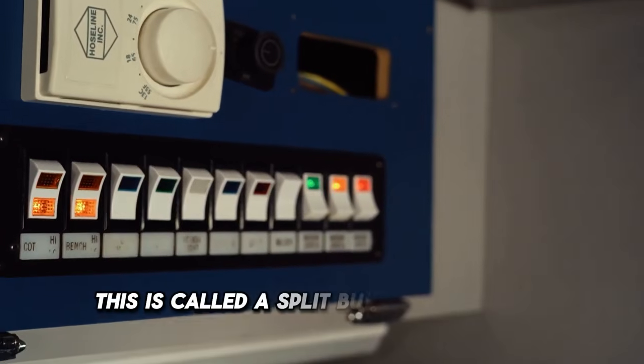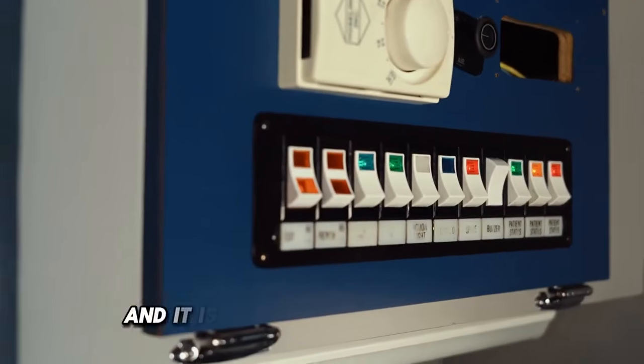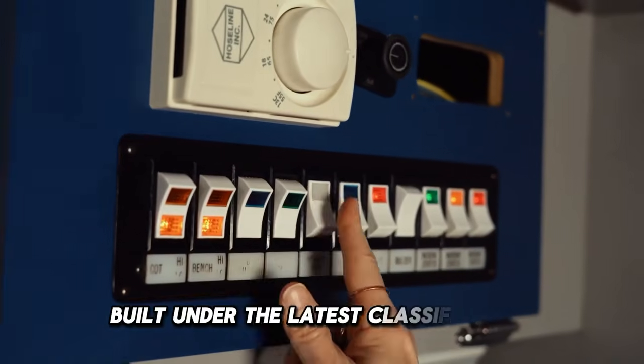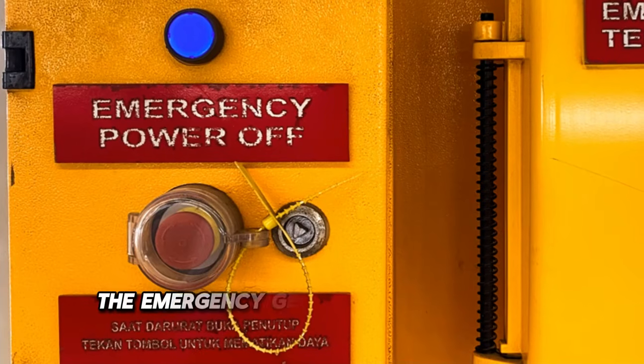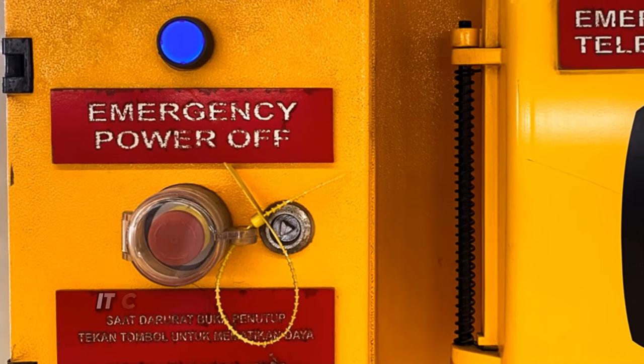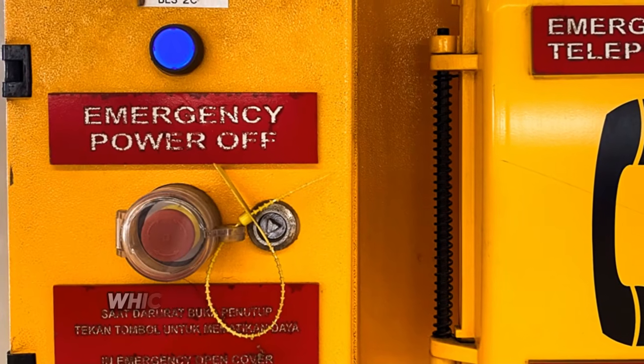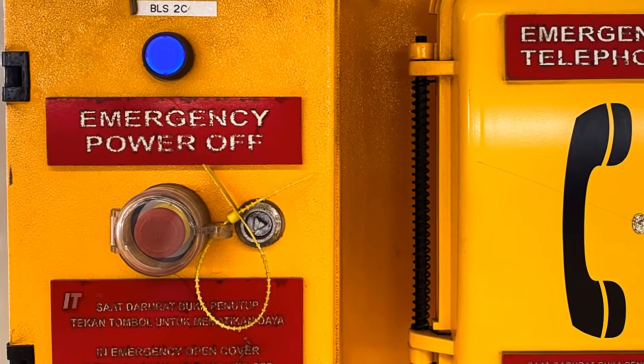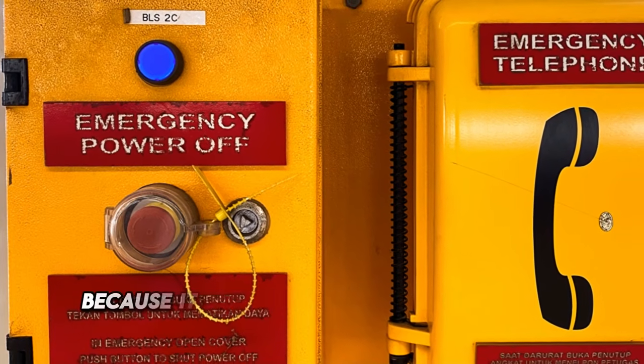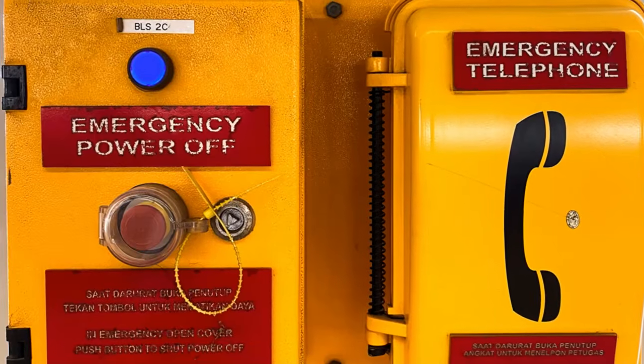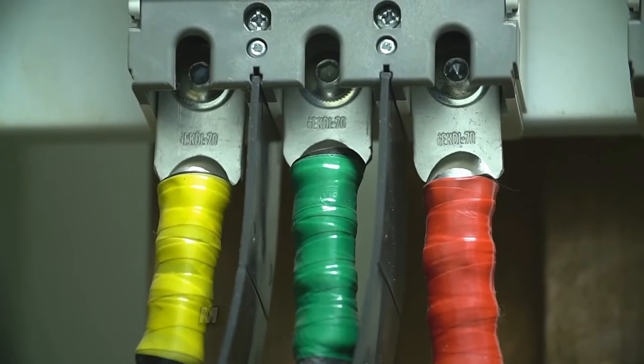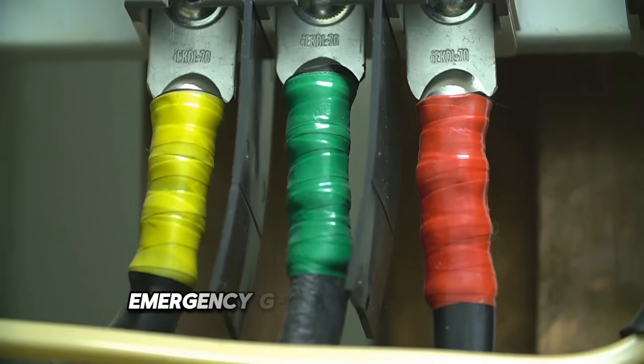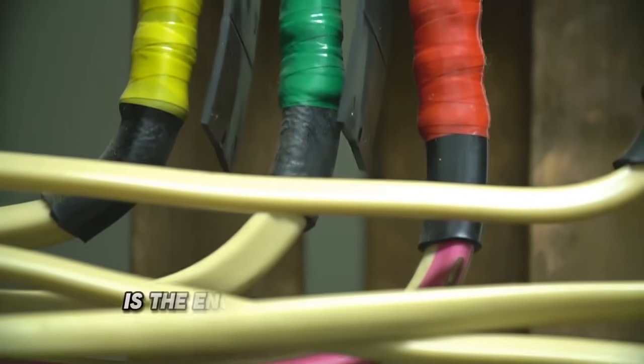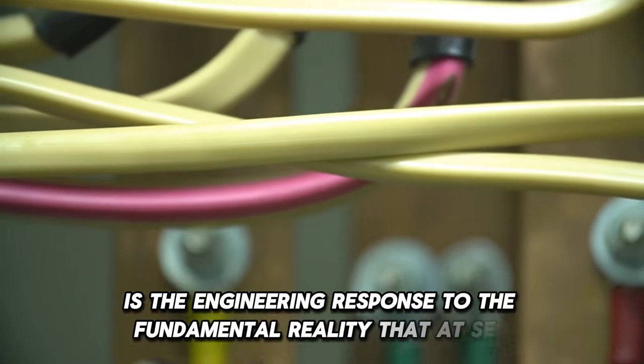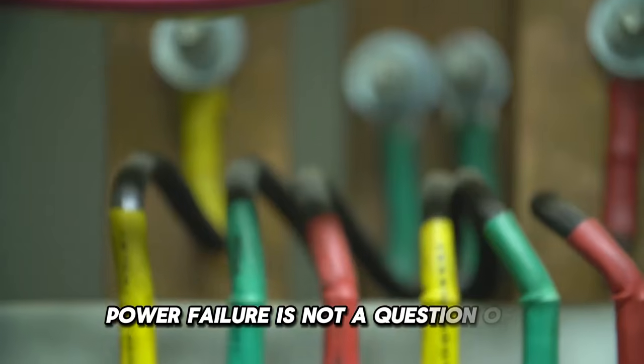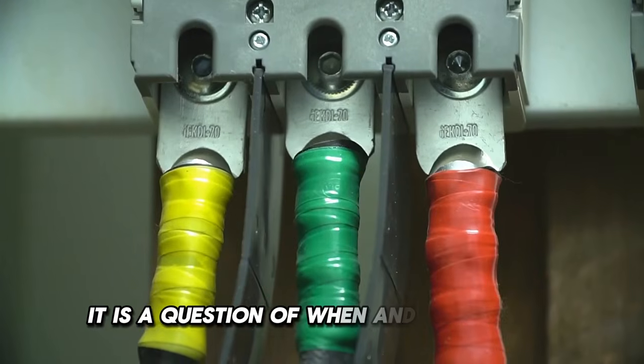This is called a split bus or closed bus configuration, and it is now standard on vessels built under the latest classification society rules. The emergency generator sits entirely outside this system. It connects directly to the emergency switchboard, which feeds only the critical safety systems. It cannot be affected by a fault on the main system because it is physically and electrically isolated from it. This layered architecture, main system, split bus, emergency generator, emergency switchboard, is the engineering response to the fundamental reality that at sea, power failure is not a question of if. It is a question of when and how severe.